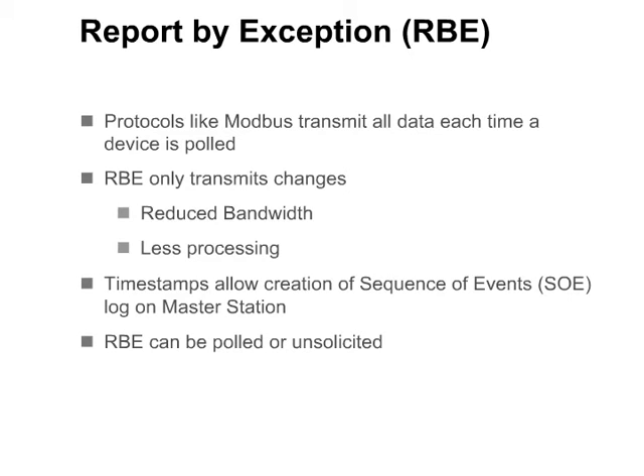Note that RBE can be either polled or unsolicited. With polled RBE, the master polls the outstation for events and only changes are reported. Although some bandwidth is used for polling, this is still more efficient than protocols like Modbus, in which the master station must poll all data. With unsolicited RBE, the outstation sends the changes as they occur, without having to be polled. Polled and unsolicited RBE will be discussed in more detail later in the course.